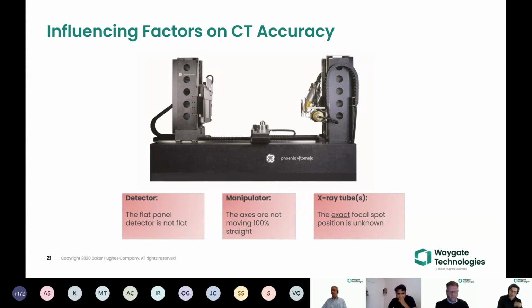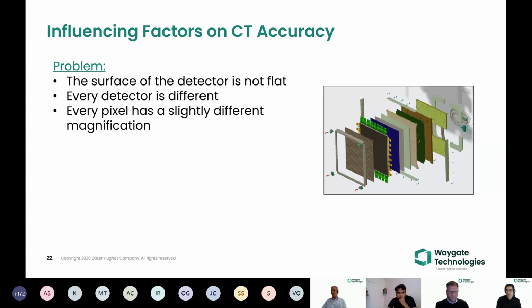So let's talk about our detector for a bit. Our detector is a flat panel detector, built by us in our GE factories in the USA. And when these flat panel detectors come out of the factory, they are not flat. They look flat and they are flat on a certain level, but we are talking again about a few microns here. A human hair is something like 80 microns, and this is way too much for us. We need something like a hundredth of a human hair diameter. So really, really tiny unflatness of this detector. But this is something that is bothering us. Why is that? Because first of all, every detector is different when it comes out of the factory.